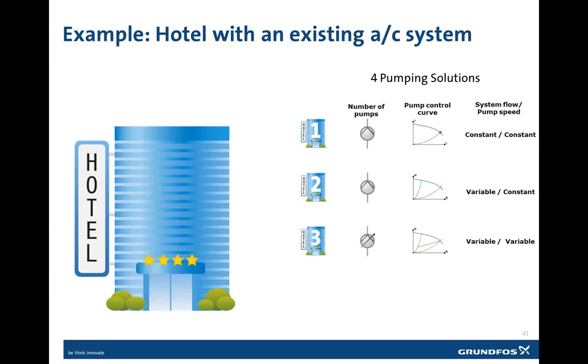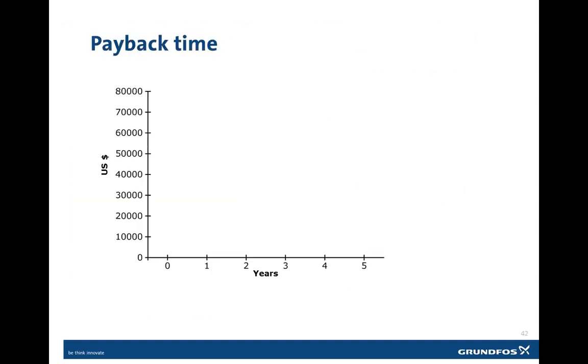And then the third method that we're going to look at is a single pump operating with variable speed and variable flow. And then the fourth selection we're going to look at is using parallel pumps. They're going to be sequenced, also using variable speed and variable flow operating controls. So first we're going to look at the payback curves for our 4 different examples.